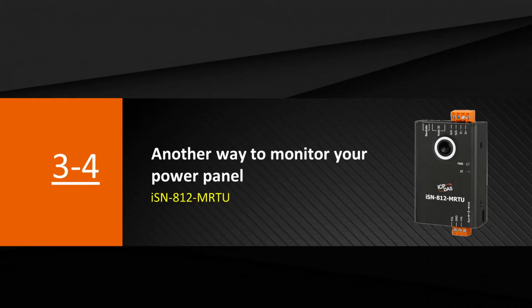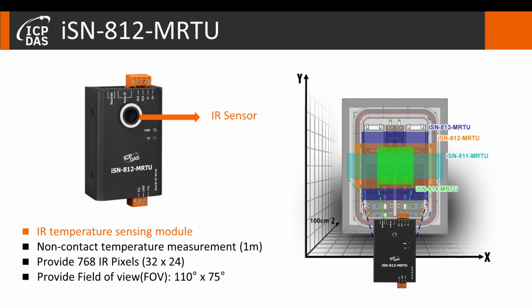Another way to monitor your power panel. To monitor the power panel, we have ISN 812 MRTU, which is an IR temperature sensing module. It's a non-contact temperature measurement module, and it provides 768 IR pixels. Instead of measuring only a small part, infrared thermometer can measure a wider area.